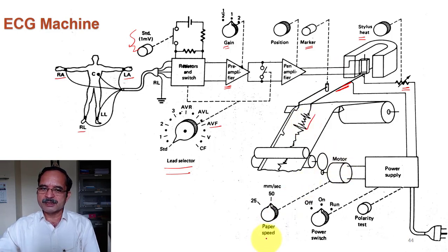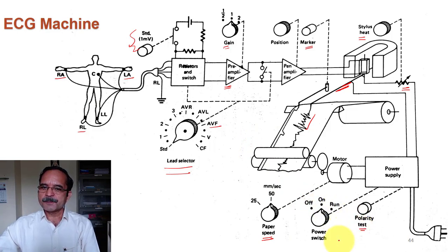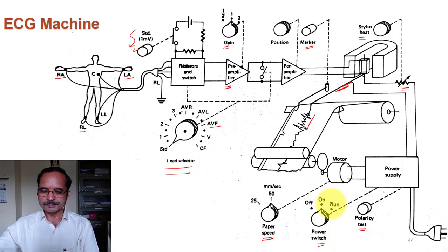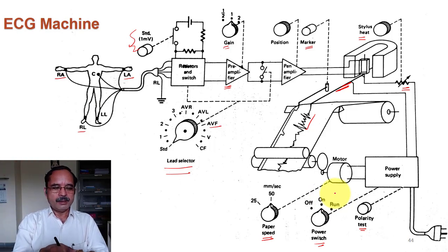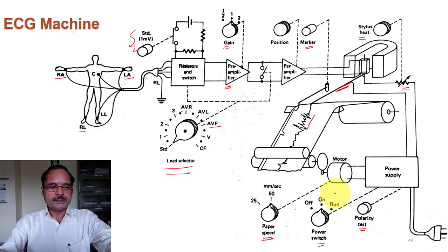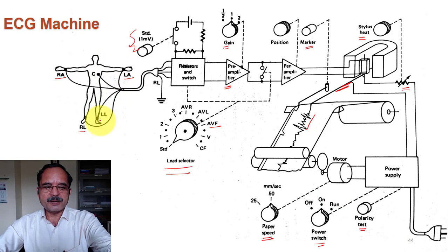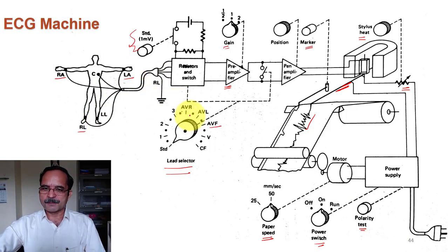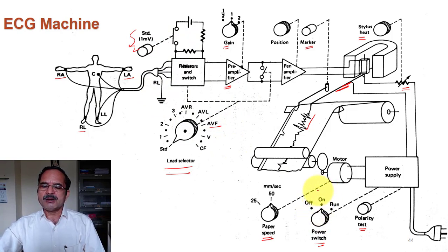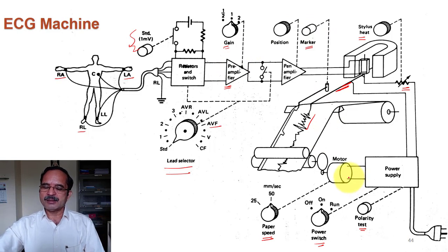There is a motor and you can adjust the paper speed. There is also a polarity test and a power switch with three positions: off, on, and run. When it is off, everything in the plotter is off. When the switch is in the on position, all circuits except the stylus are working. When in run position, actual plotting will start.